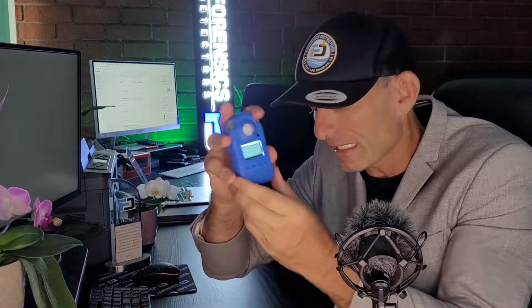Okay, that's basically, now what do you get? Okay, you get the detector in a nice cardboard strong box. It comes with the manual. It comes with your calibration certificate, which is very important. We calibrate to our special ozone NIST calibrated generators and analyzers here in Los Angeles, folks. Ozone needs unique equipment for calibration. You cannot buy ozone in a bottle. It doesn't work that way. No, ozone is a unique beast. I explain it on our website. I actually have a little piece on that on our website.